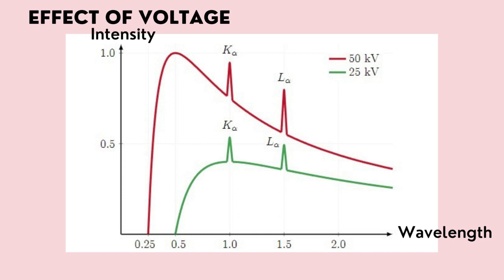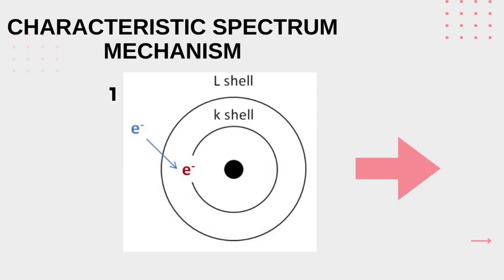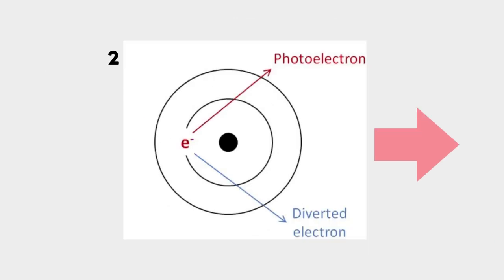The peaks are due to electrons from the cathode knocking out inner shell electrons from target atoms. When vacant shells are refilled by free electrons, x-rays are emitted. The electron ejected from the cathode collides with the free electron at orbit K, and the free electron is knocked out from the orbit. There is now an empty space at orbit K.